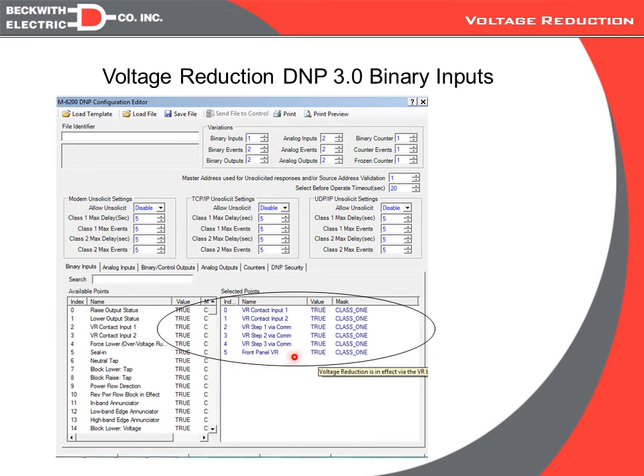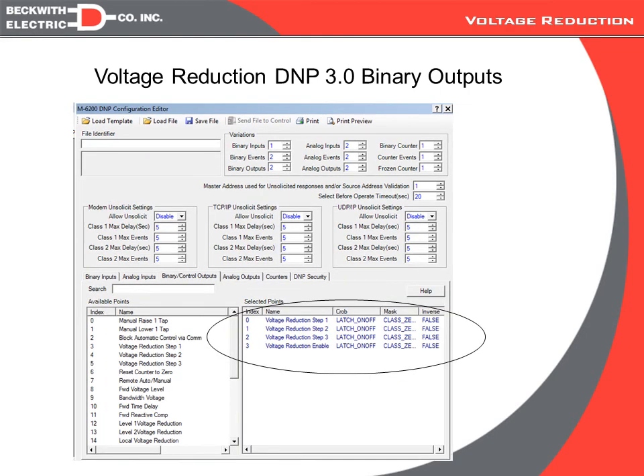So if this was a 1, it would tell me the voltage reduction is being applied via the front panel. I wouldn't know necessarily what level, but I know it was applied via the front panel. A 0, and I know it's not being applied via the front panel. Likewise, these two hardware inputs would tell me whether the voltage reduction is being applied via the hardware inputs. And finally, these three would be a 1 if via SCADA it was in voltage reduction via any of the three steps. So those are the binary inputs that we would want to monitor typically with voltage reduction.